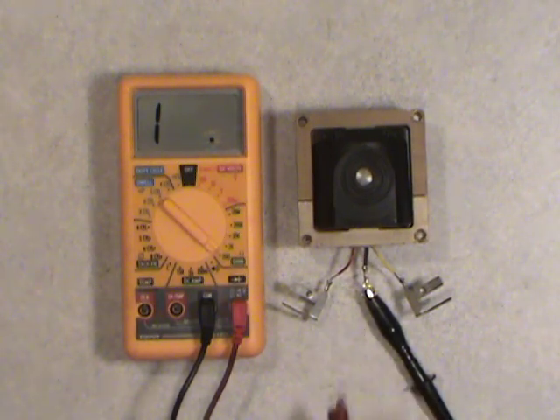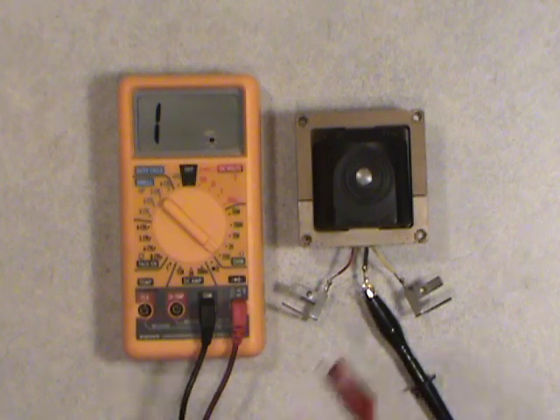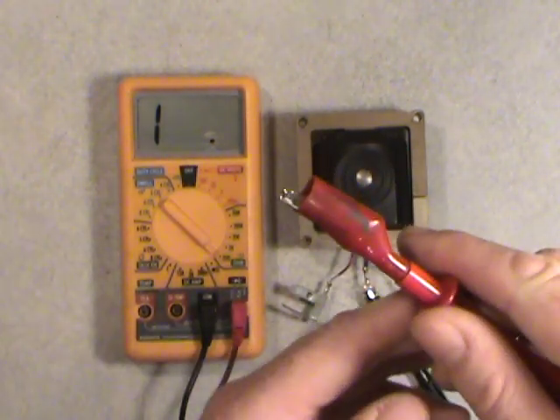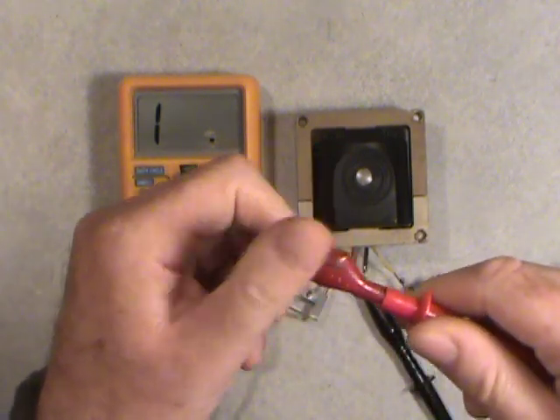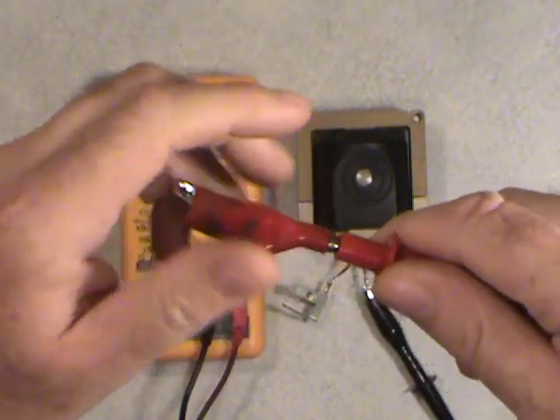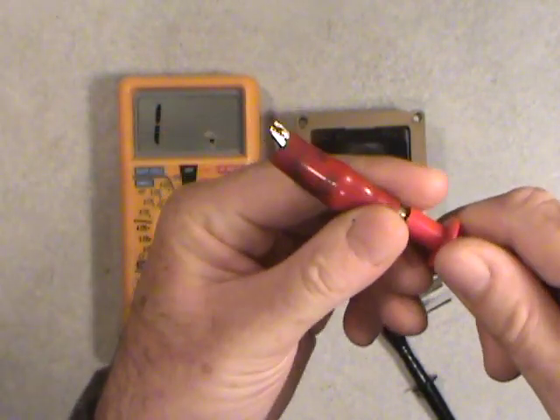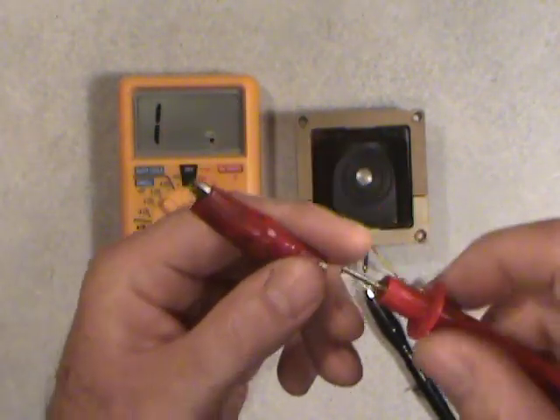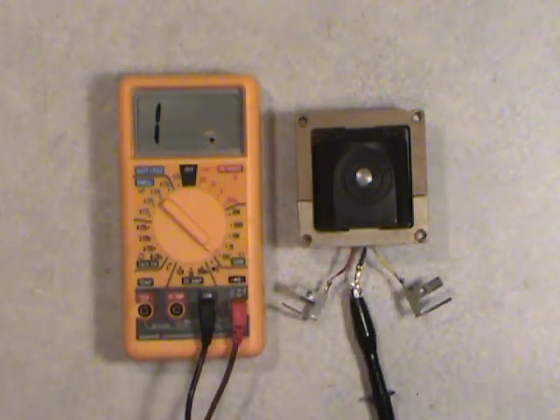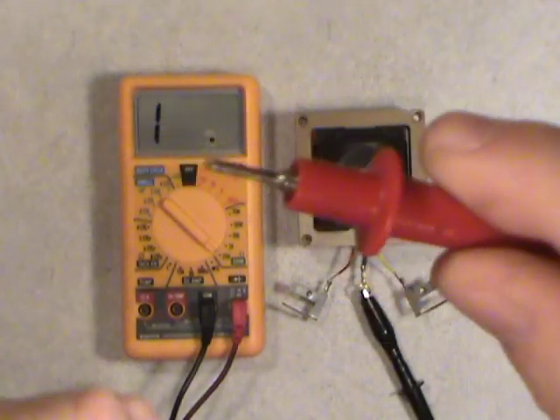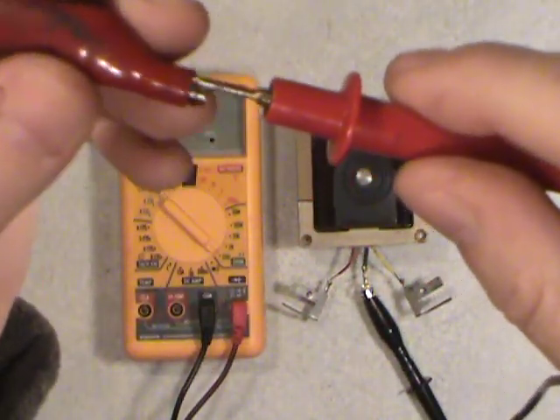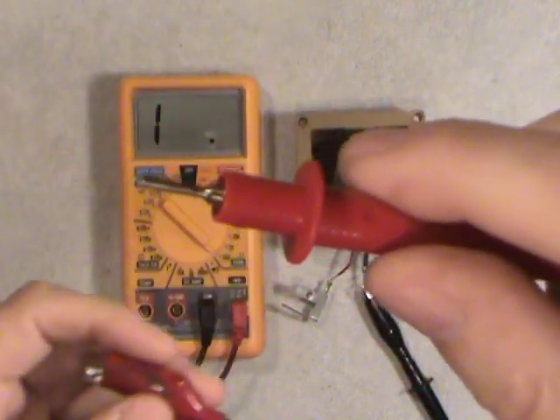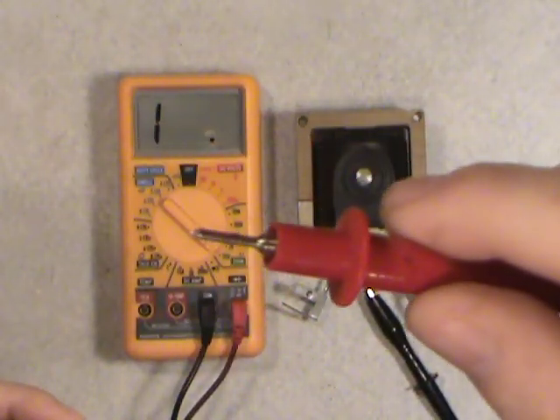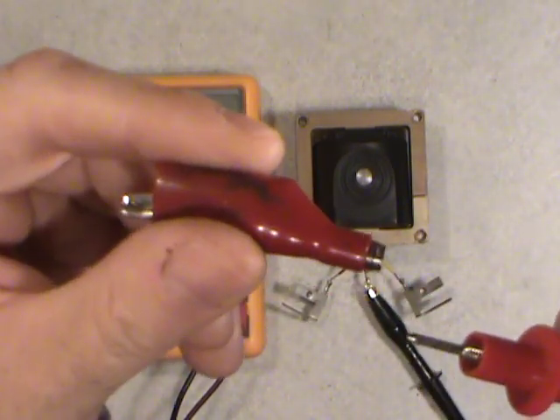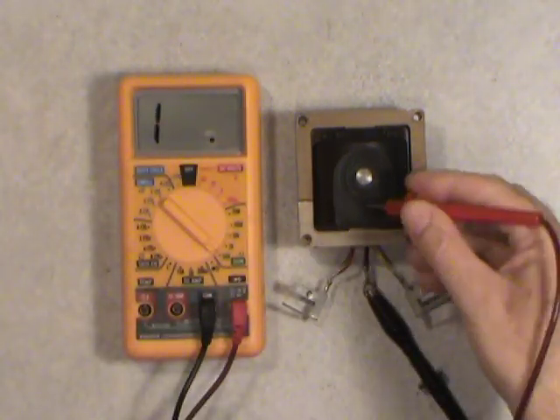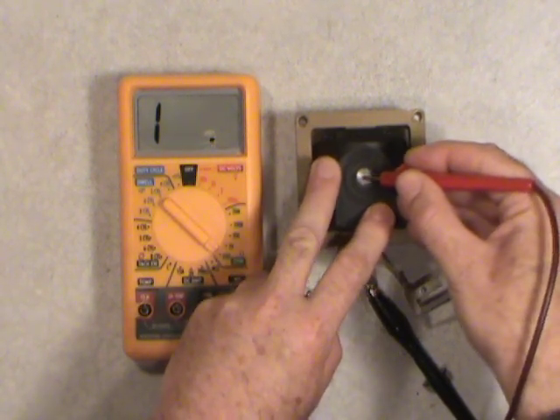Okay, so we've got that hooked up onto the ground. Now we're going to do the high ohm reading. I could just go in with the Alligator Clip, but I'm going to show you, I'd mentioned in the other video that these unscrew. Both of them do on the black and the red test probes here. So you can have the Alligator Clip if you can clip on, but if you have to get in somewhere small, there's, excuse me, I'm a little caught up in the wiring here. Okay, here we go. See, this just screws on here like so, and then you just unscrew it, and then you've got a probe to get down to smaller parts here. Okay, it's just like a small nail. So I'm just going to park the Alligator Clip head off to the side, and we're going to scratch into the secondary side here to make sure we make a good connection here.